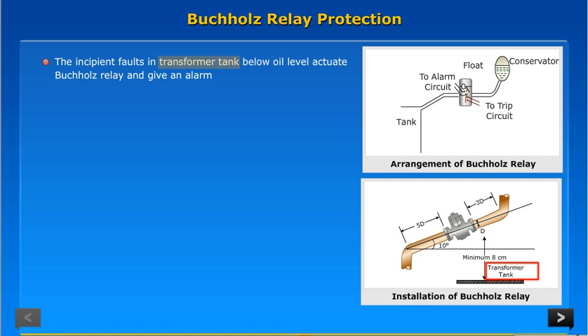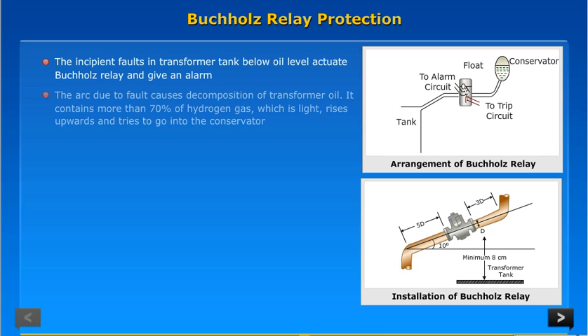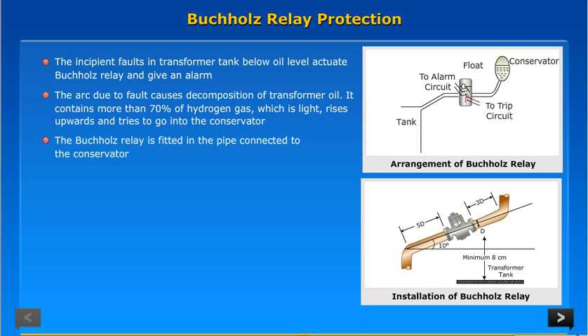Buchholz relay protection. The incipient faults in transformer tank below oil level actuate the Buchholz relay and give an alarm. The arc due to fault causes decomposition of transformer oil. It contains more than 70% hydrogen gas, which is light, rises upwards and tries to go into the conservator. The Buchholz relay is fitted in the pipe connected to the conservator.